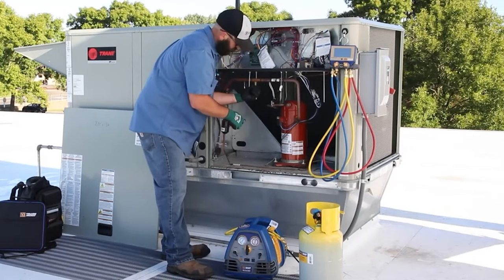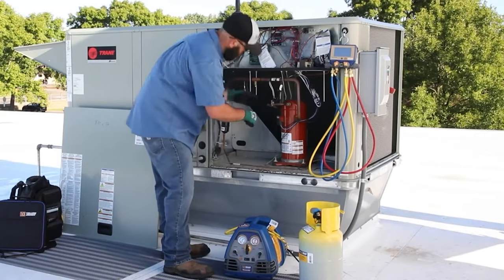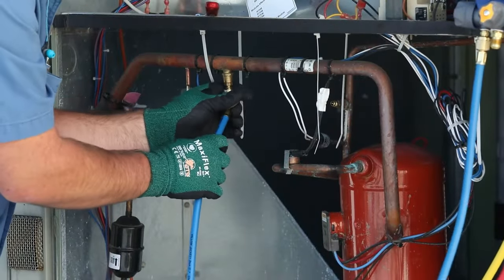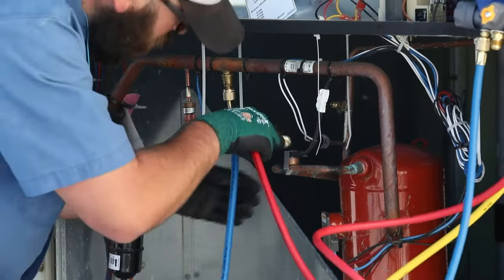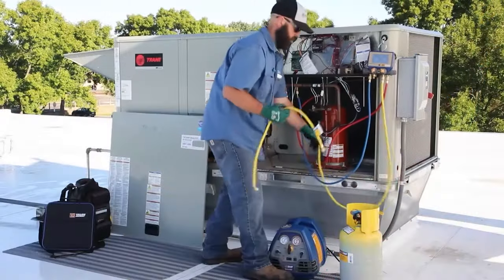Remove the service port caps and connect the manifold hoses to the corresponding service ports: blue for low side, red for high side. Then connect the manifold charging hose to the suction port of the recovery machine.